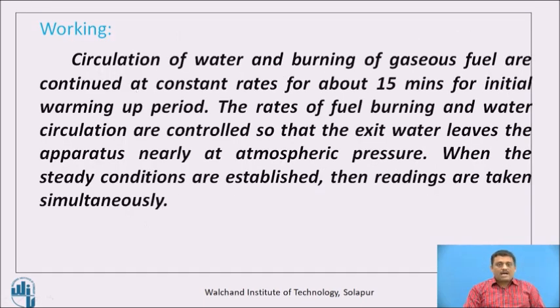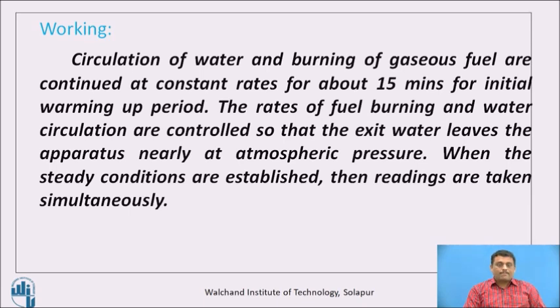Now we will see how it works. First, the circulation of water and burning of gaseous fuel are continued at constant rates for about 15 minutes for the initial warming-up period. The rates of fuel burning and water circulation are controlled so that the exit water leaves the apparatus nearly at atmospheric pressure. When steady conditions are established, the readings are taken simultaneously.